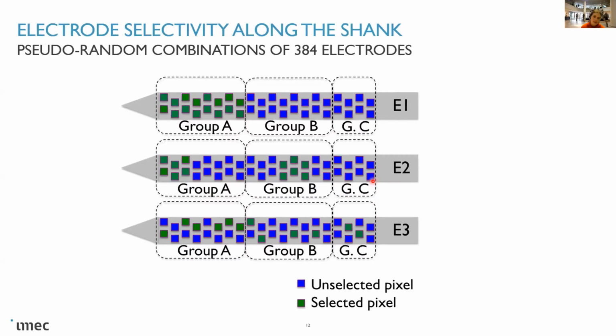Something important to understand is that in these probes we have 3 subsets of groups that are sharing the same channel. So electrode number 1 from this group is sharing the same channel as electrode number 1 here, meaning that these 2 cannot be selected at the same time. But you can still select groups that are not overlapping and spread them. You can also select individual electrodes completely spread, as long as you don't overlap the common channels.